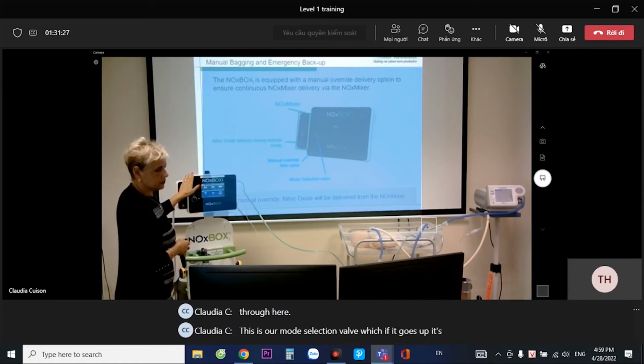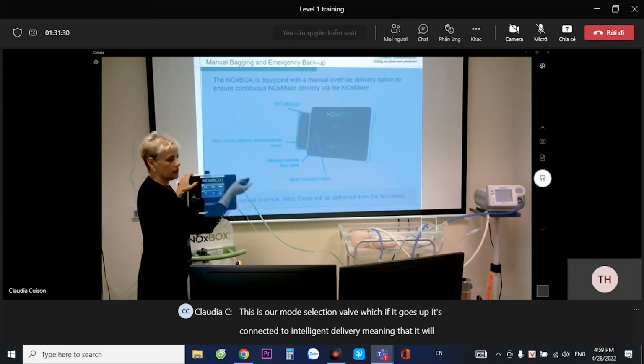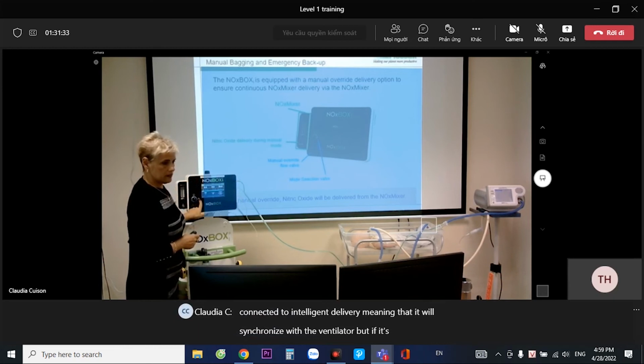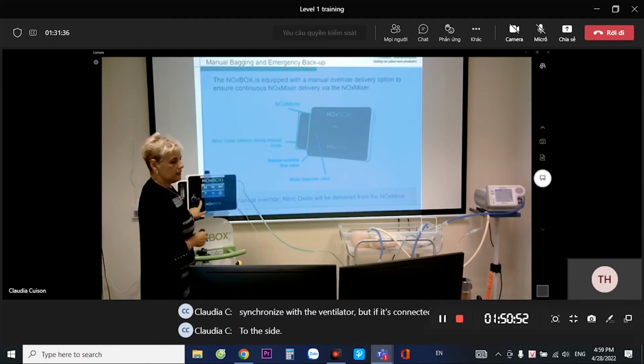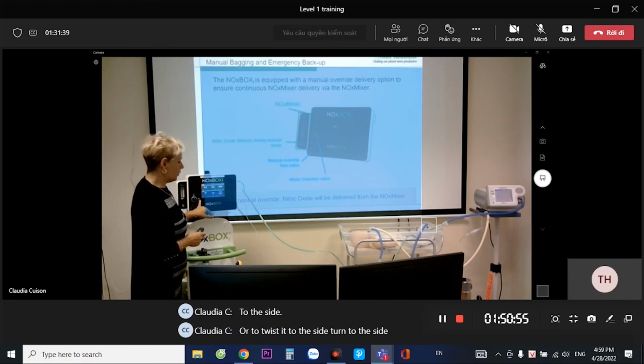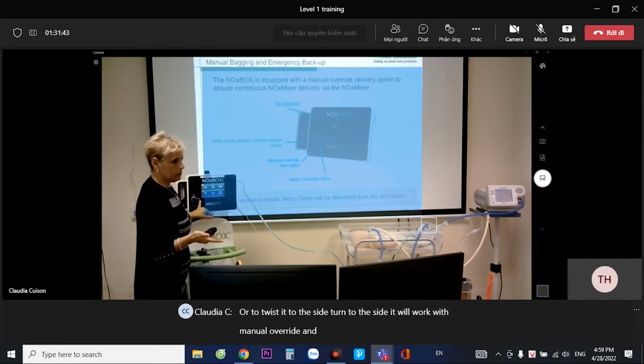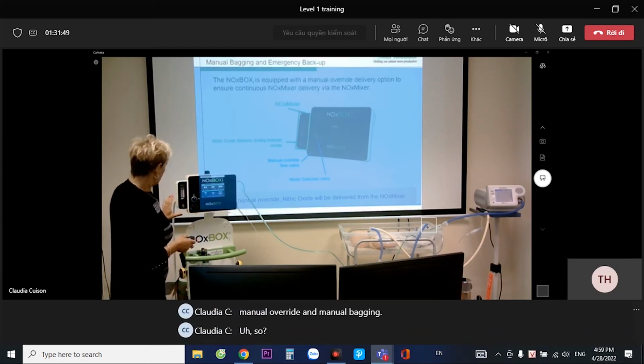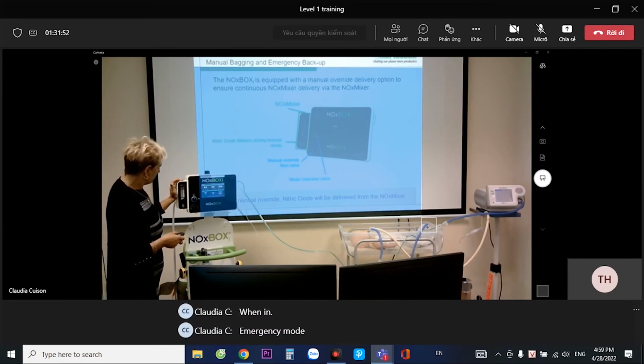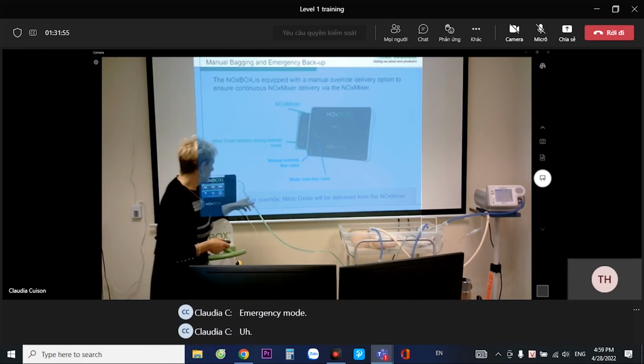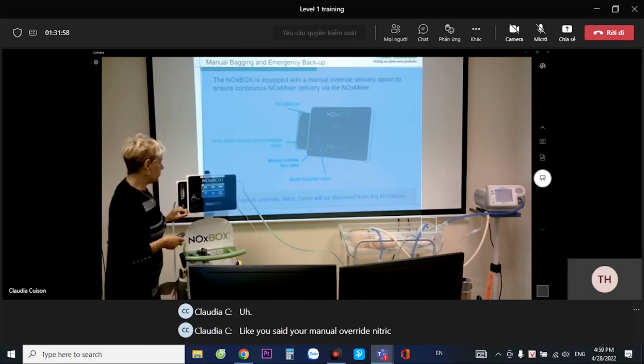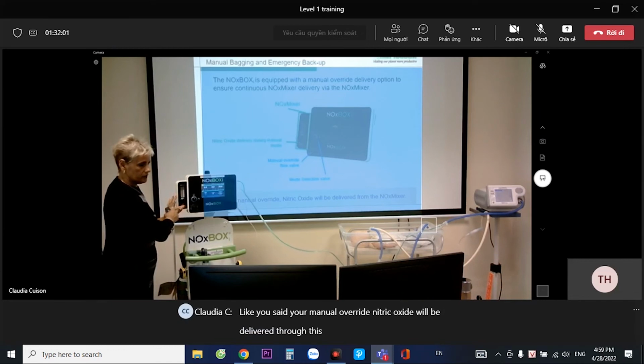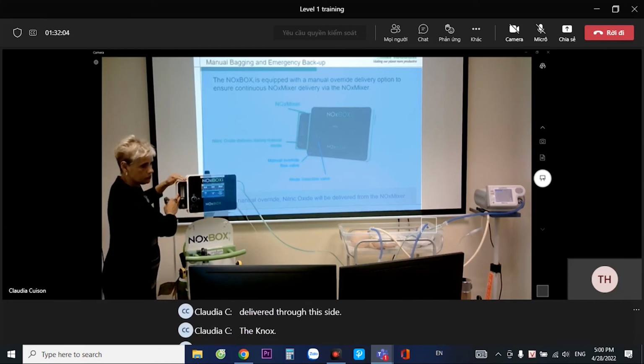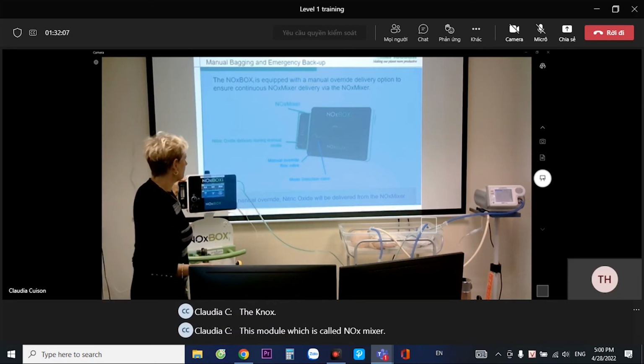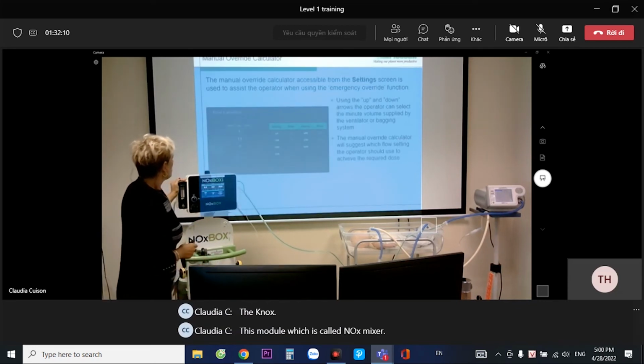This is our mode selection valve, which if it goes up, it's connected to intelligent delivery, meaning that it will synchronize with the ventilator. But if it's turned to the side, it will work with manual override and manual bagging. So when in emergency mode, like I said, your manual override, nitric oxide will be delivered through this side, through this module, which is called the NOx mixer.